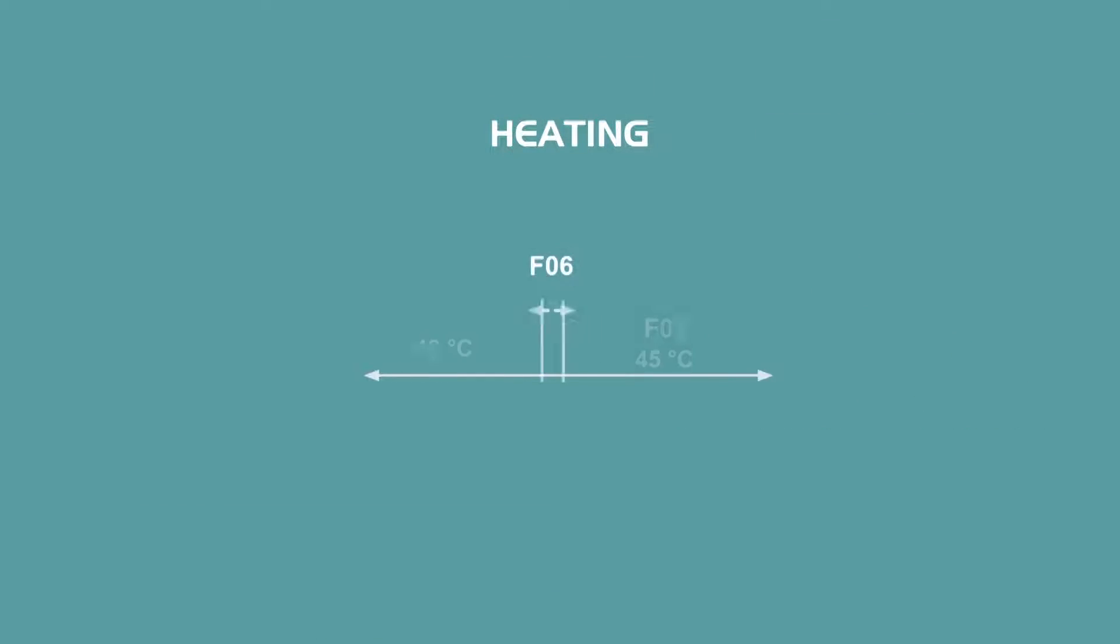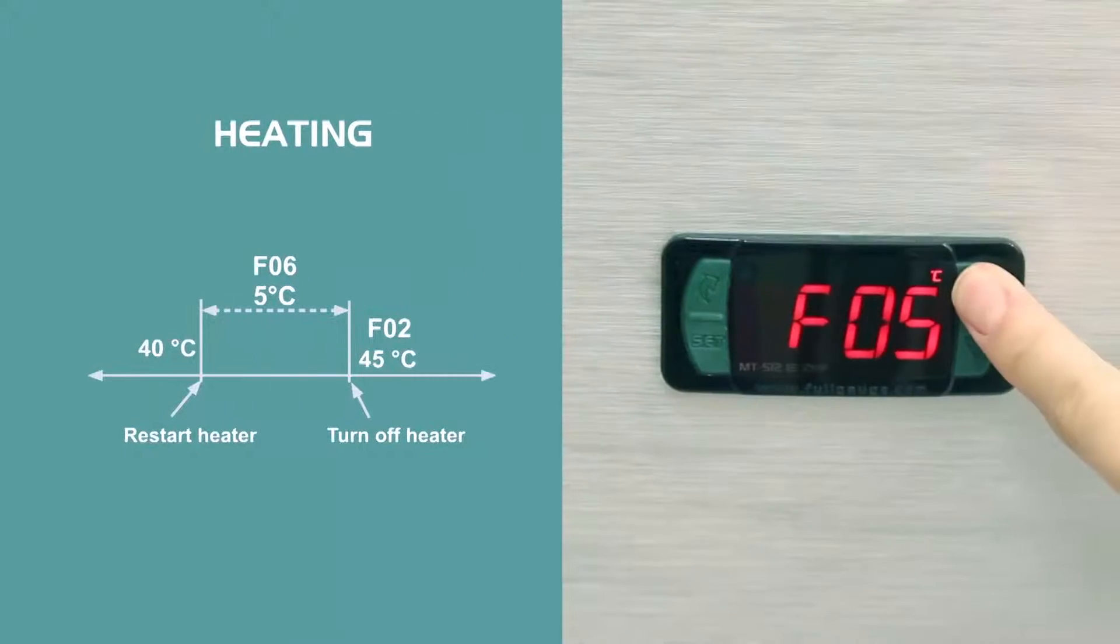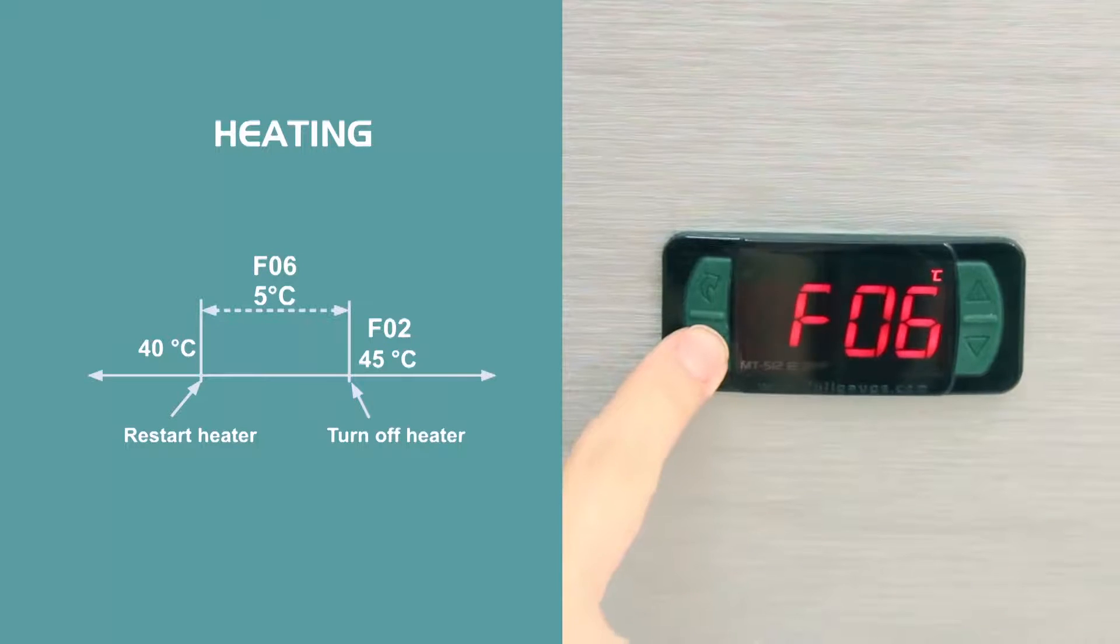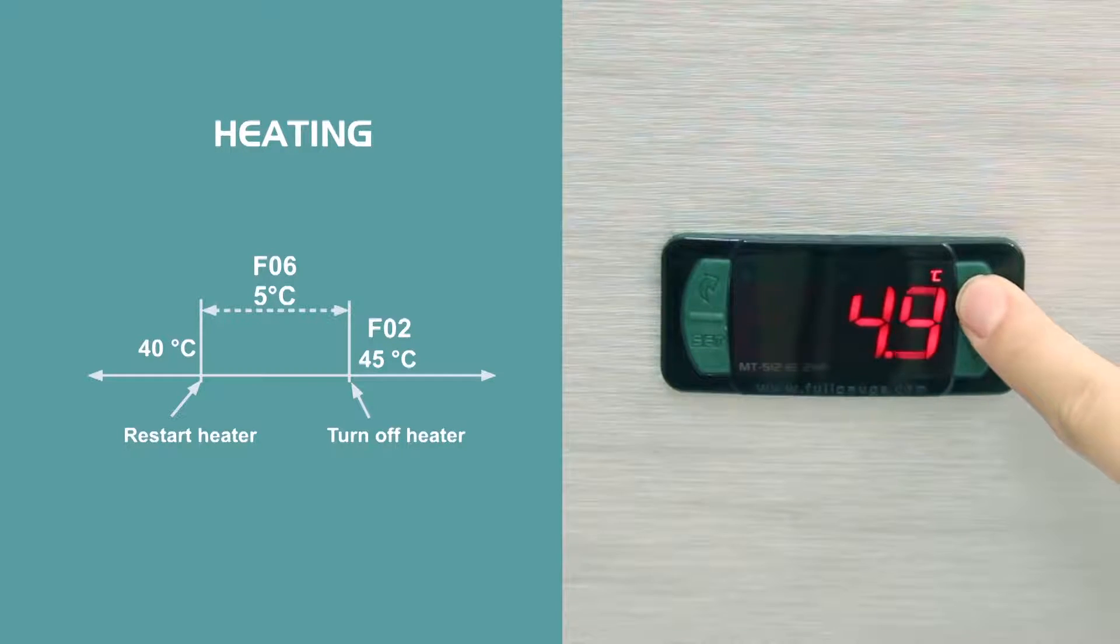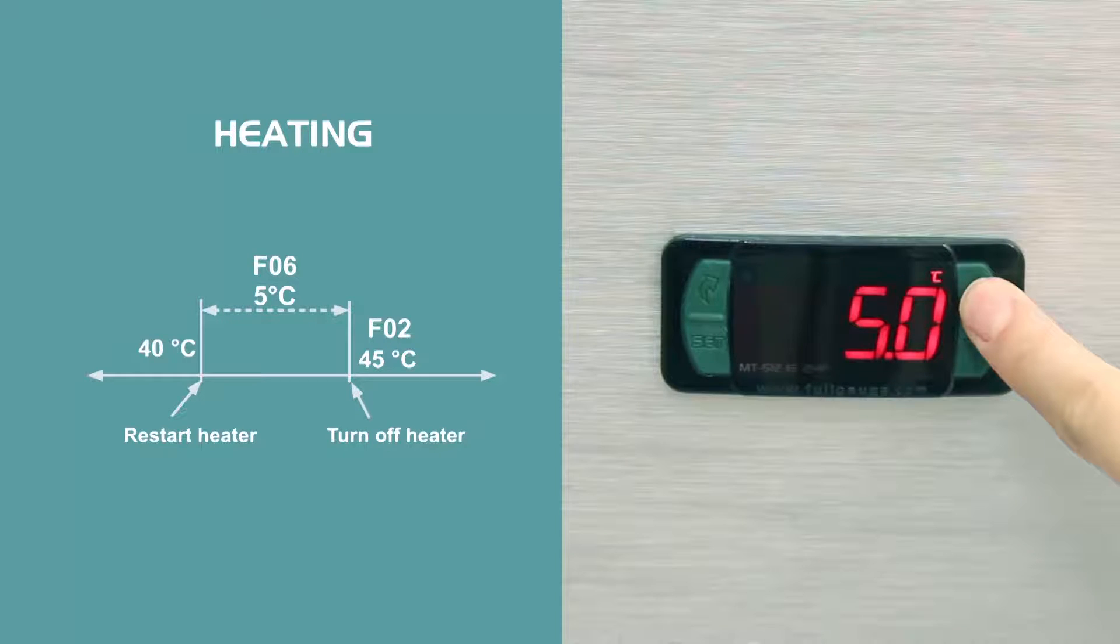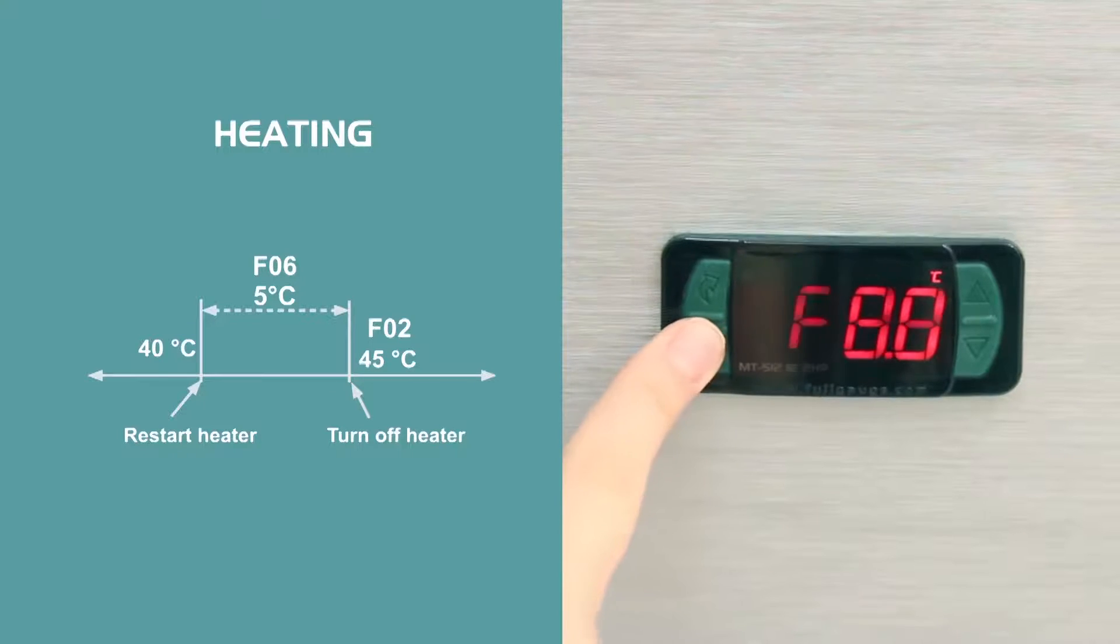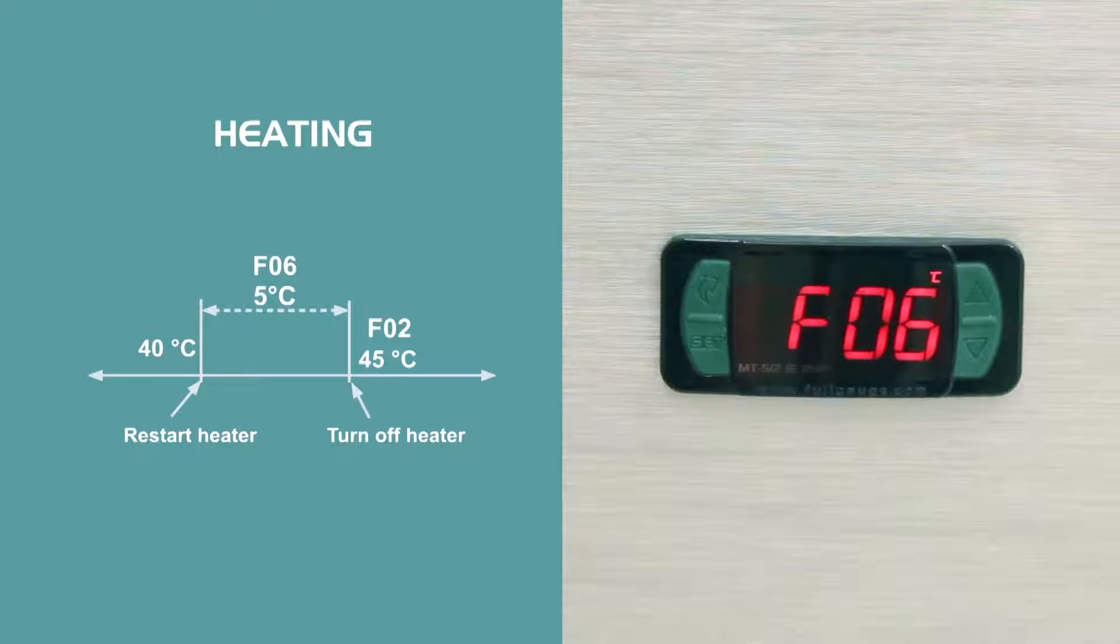In the heating example, with a set point of 45 degrees Celsius and the hysteresis adjusted at 5 degrees Celsius, the controller shuts down the heater at 45 degrees Celsius and reconnects it at 40 degrees Celsius. Note, a very low hysteresis results in high frequency in the controller relay activation and deactivation cycles, which can shorten the life of the components.